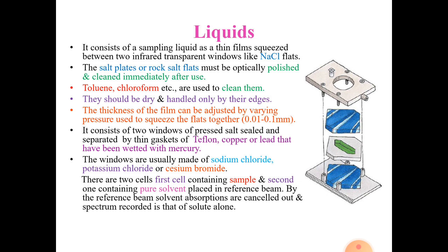The salt plates or rock salt flats must be optically polished and cleaned immediately after use. To clean them, you can use toluene or chloroform, and we have to keep the entire setup dry and handle it only by the edges.